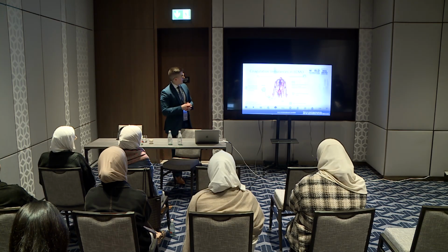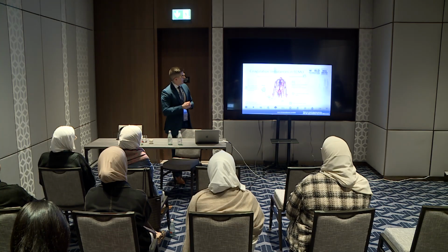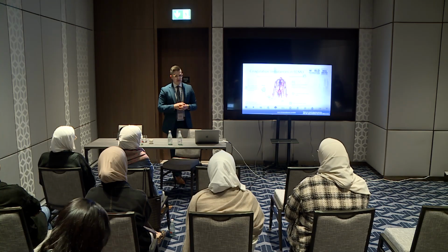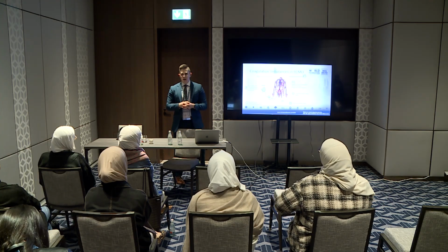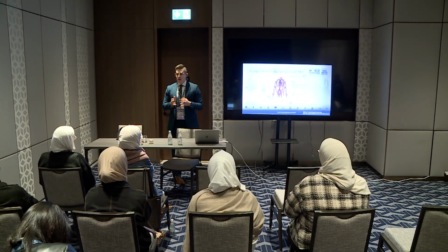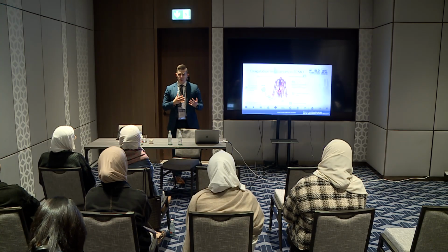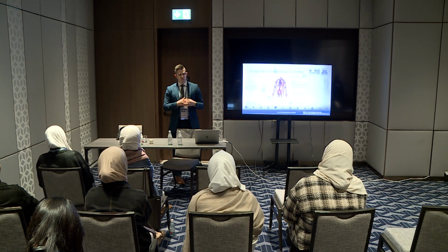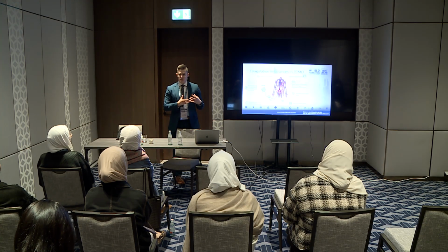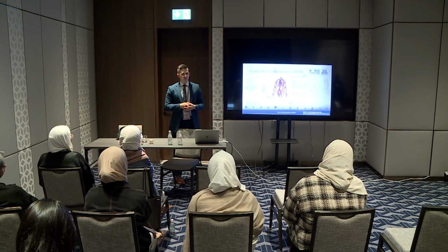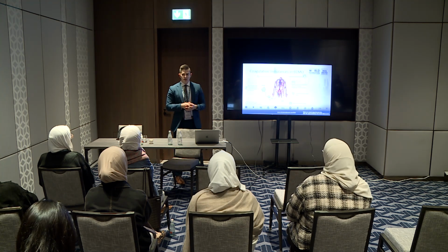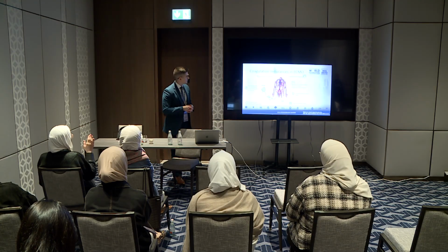And also, like we just talked about before, intraventricular blood stasis is a problem if we're providing VA ECMO for cardiac support and the patient has very severely impaired heart function. The blood can pool in the cardiac chambers, and this can be catastrophic if thrombosis occurs.